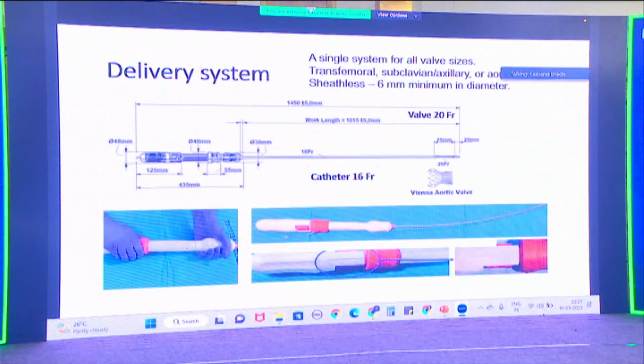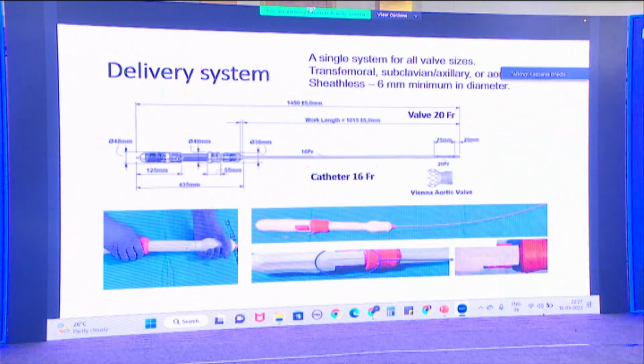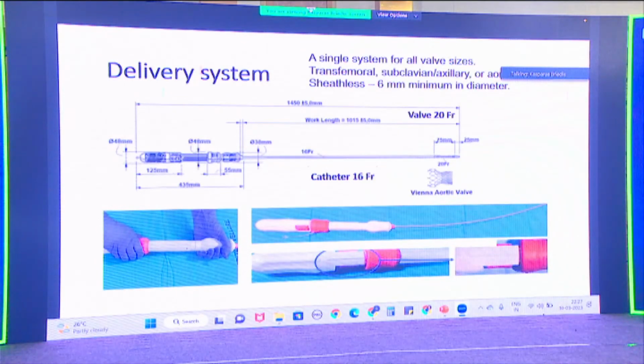And the same delivery system as for the TRI valve. Basically one knob, because you need to rotate clockwise for the valve to be fully released, and if you want to recapture the valve, you can just turn it counterclockwise. It is 16 French in the shaft and 20 French in the distal end, where the capsule and the valve are crimped. So I think it will be covered in upcoming slides.